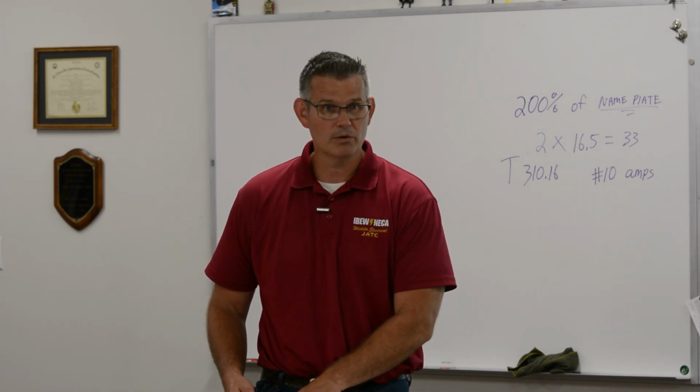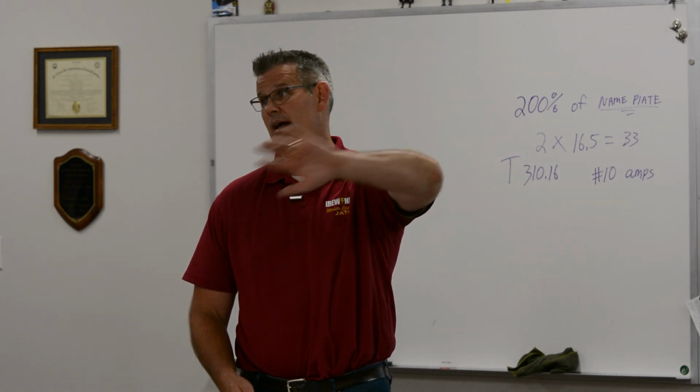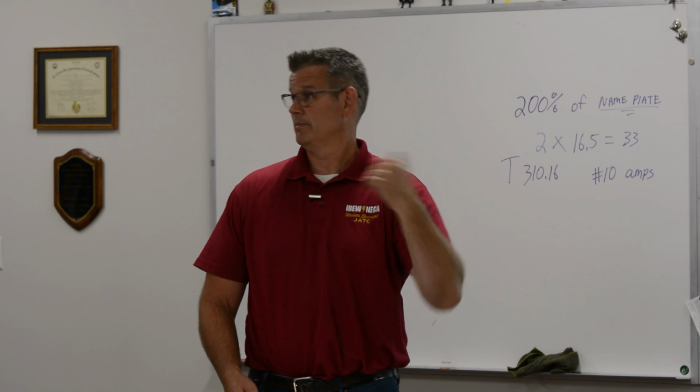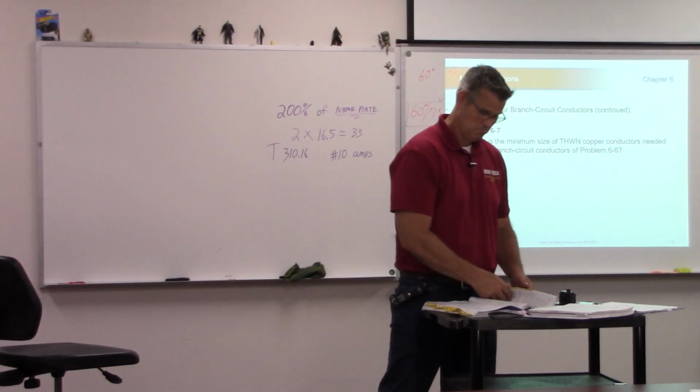Table 240.4(G) and 240.4 said so. 240 doesn't apply to overcurrent protection for motors unless 430 references something there. So, small conductor rule, gone. So, you could use tens. I could use 10s. Would you use them? Sure.